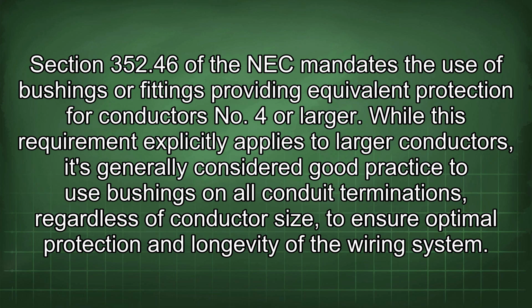Section 352.46 of the NEC mandates the use of bushings or fittings providing equivalent protection for conductors 4 AWG or larger. While this requirement explicitly applies to larger conductors, it's generally considered good practice to use bushings on all conduit terminations, regardless of conductor size, to ensure optimal protection and longevity of the wiring system.